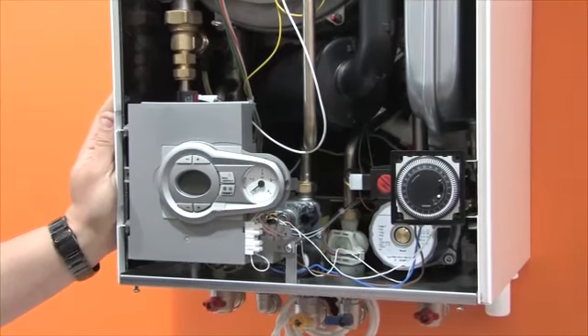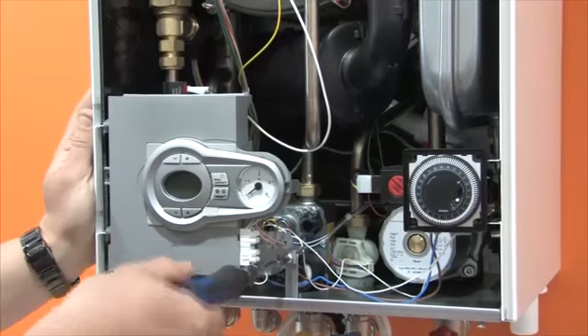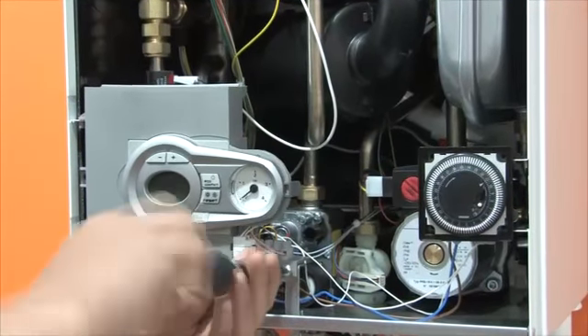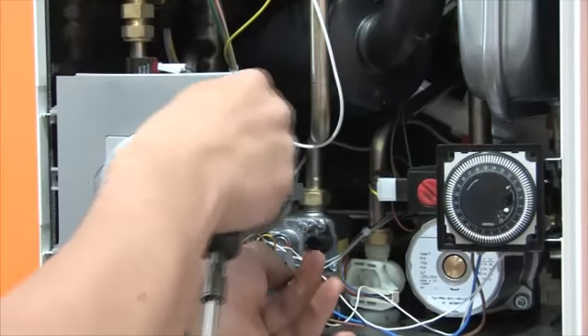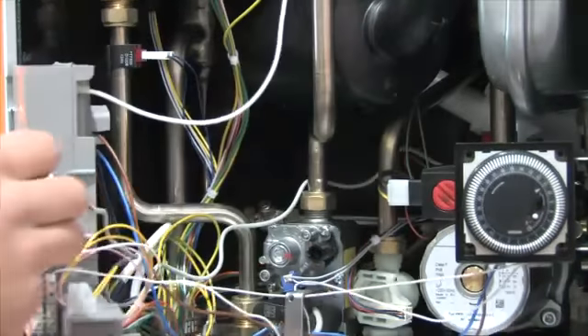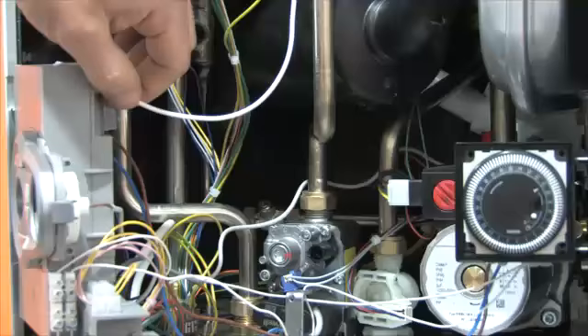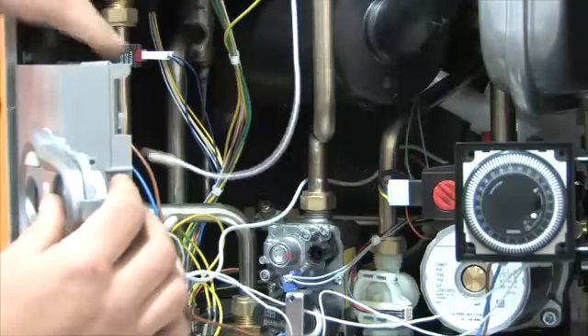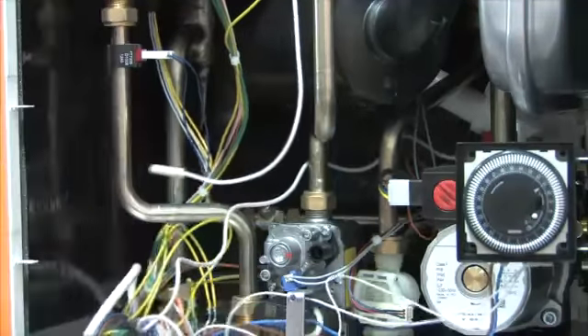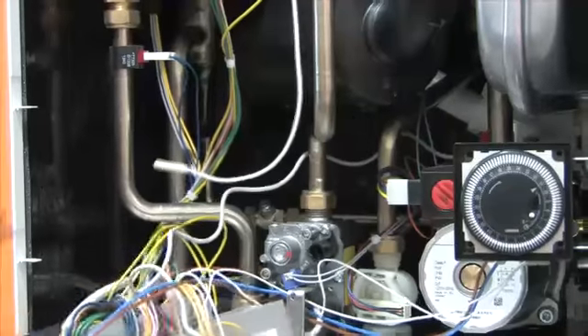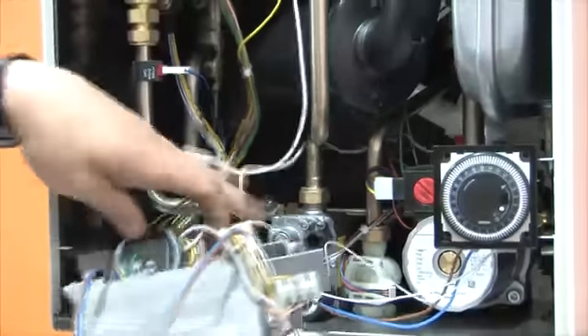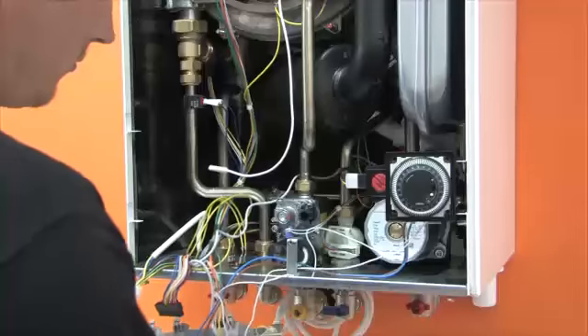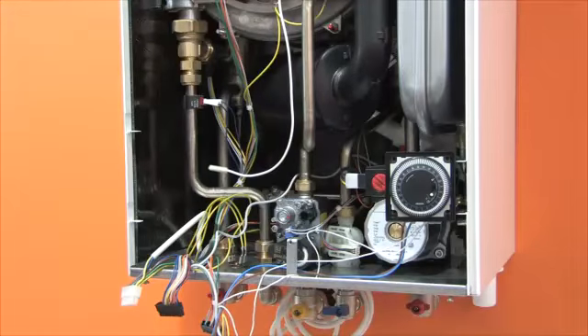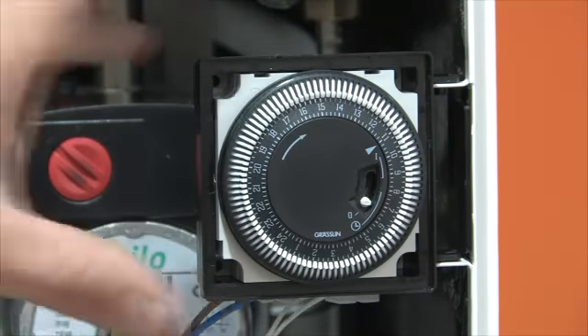The brains of the boiler is the multifunctional PCB, next to which is the pressure gauge for easy viewing without removing the casing. When working with water, the PCB can be safely moved out of the way by undoing 1 screw. Remove the PCB by unclipping the ignition electrode, remove 3 clips on the bottom and open the access panel. All internal electrical connections can then be removed. The housing for the clock, either mechanical or digital, is also easily lifted away.